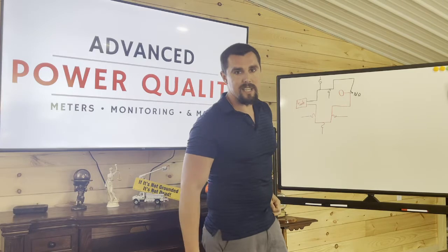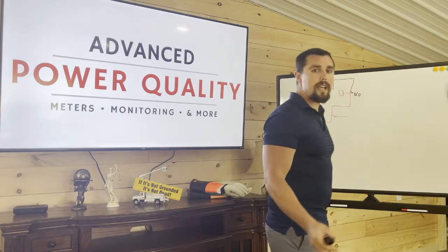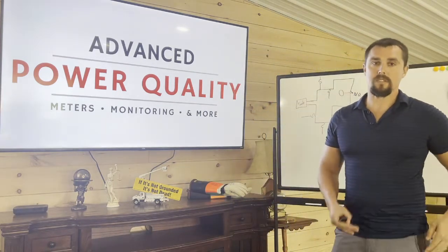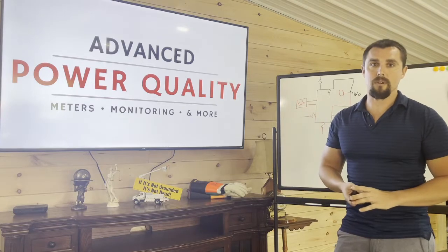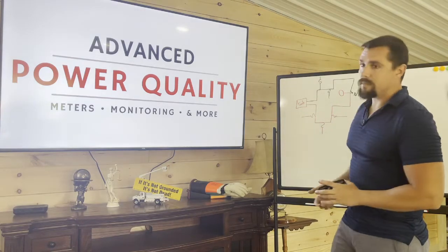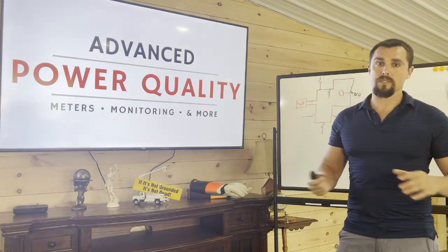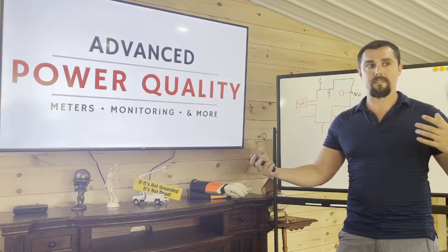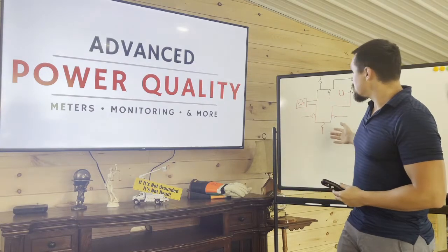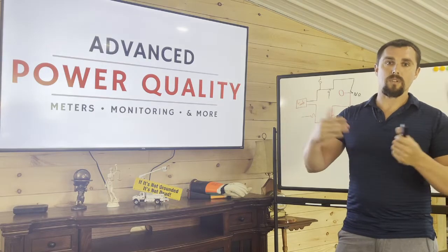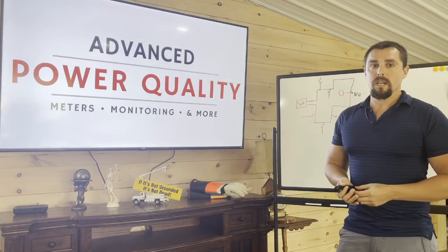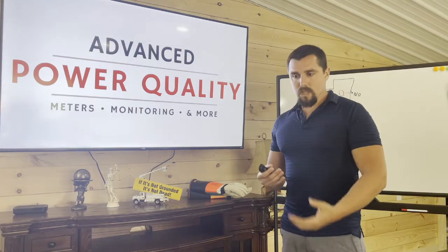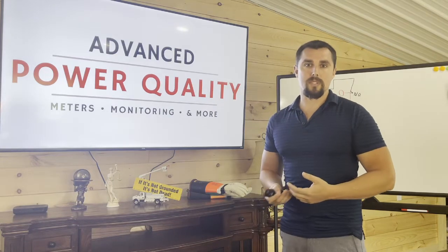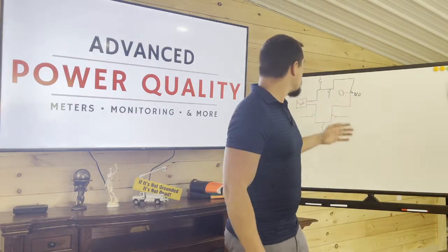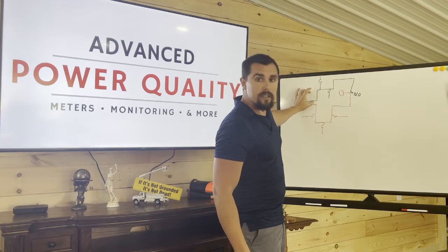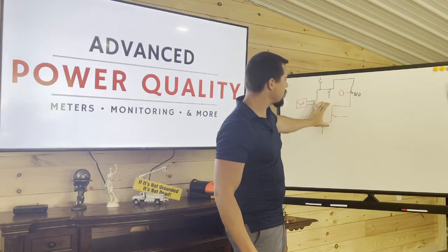Now it's a little bit more complicated than that. You typically have 8 to 10 feeders coming out of a substation, depending on how rural of an area you are. And there are tons of normally open points all over, connecting different feeders and such. Even feeders going to different substations with normally open points in the middle. Now, why I say 20 to 40% is because this allows the black feeder here to pick up the entire load of the red feed here.